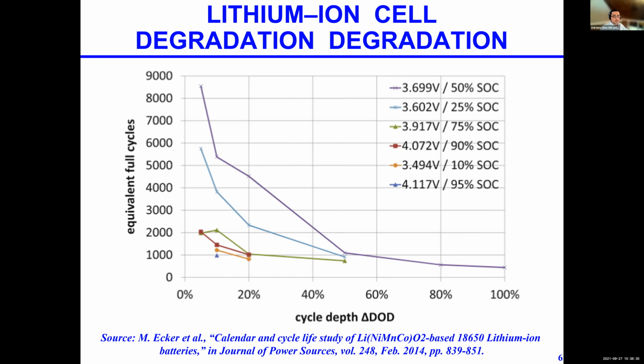And so what we do over here is we check, once the battery is following a specific charge-discharge schedule, how deep the cycles it is performing are, and we associate the loss of life of the battery, according to the depth of these cycles, to a dollar value based on how much it costs to replace the battery.